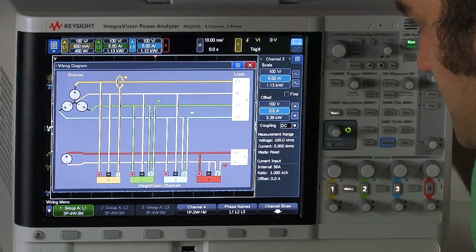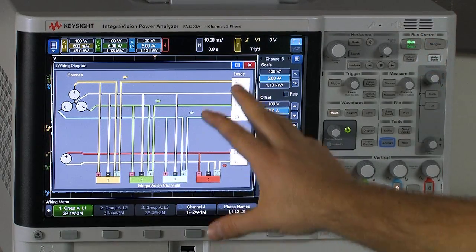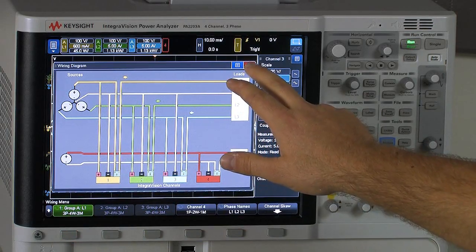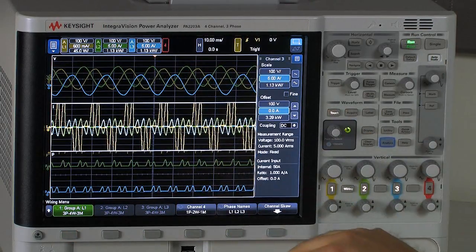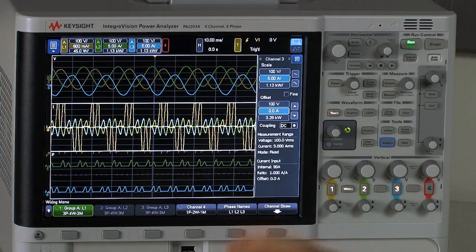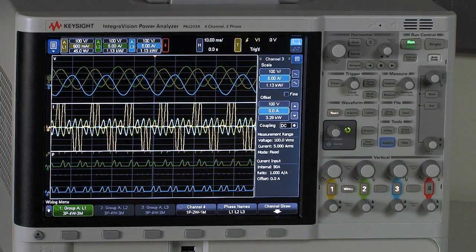So I'm just going to adjust the shutter here on the back of the instrument. And right now, so again, we have channels one, two, and three groups. I'm going to go ahead and close the wiring diagram. I have some simulated data up here on the screen. And what we're actually looking at is the input to a three-phase rectifier right now.